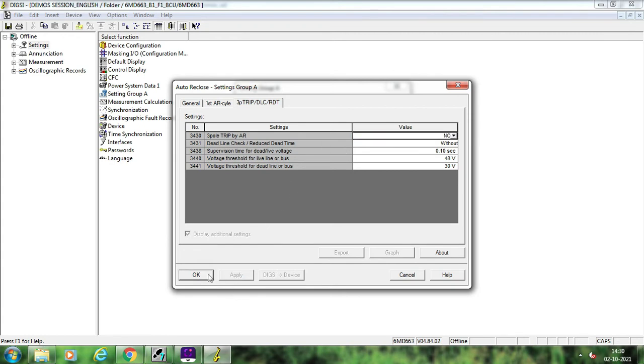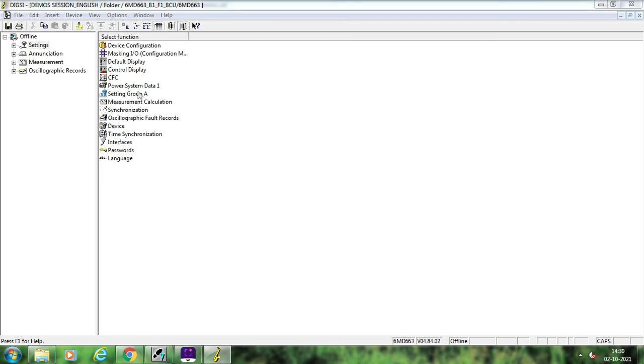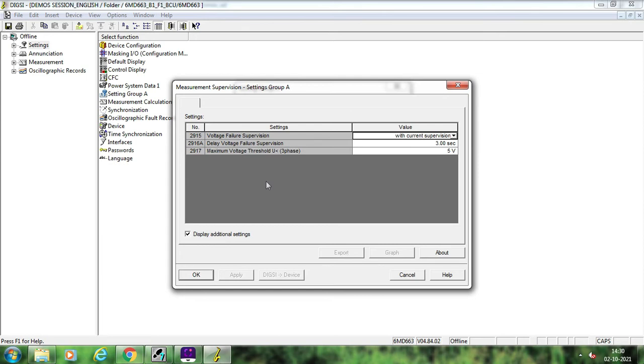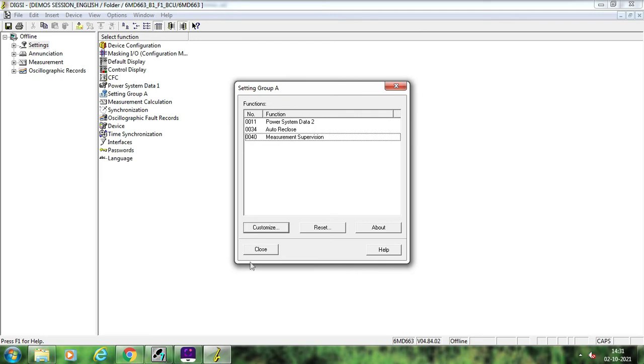Next we move to measurement supervision. The measurement supervision setting is for voltage failure supervision or VT fuse fail. The voltage fuse failure will be detected based upon current supervision — if the current is more than the pole open current threshold, for example the setting is 0.1 and current is flowing at 0.11 A secondary, and your voltage drops below the maximum voltage threshold setting of suppose 45 V, then the relay will detect it as voltage failure and you will get a signal after three seconds.